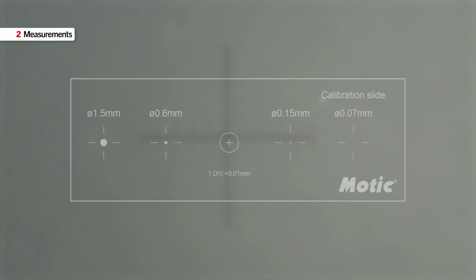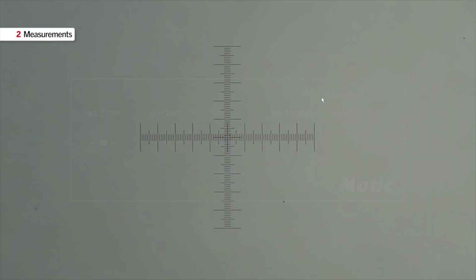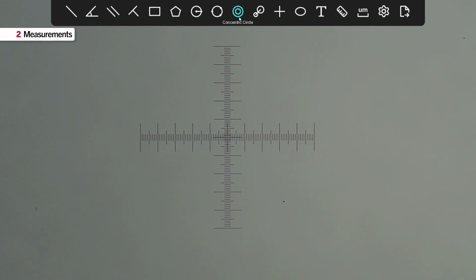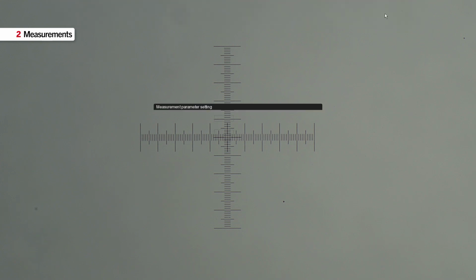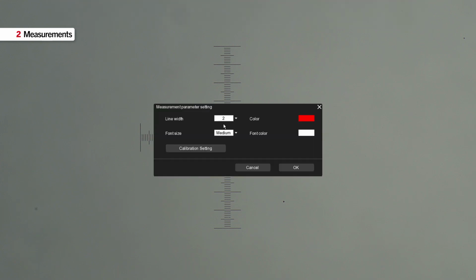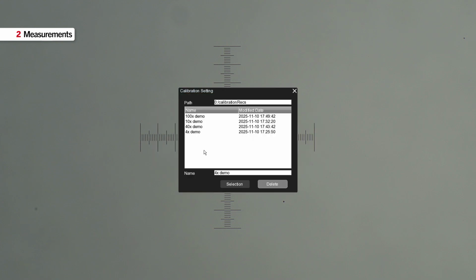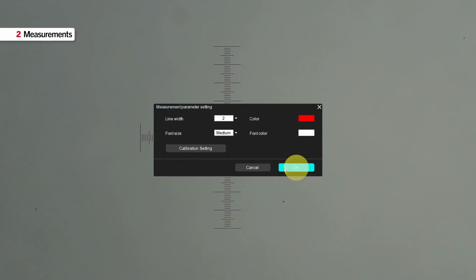To demonstrate this, we'll continue using the same micrometer cross from the calibration slide that comes with the camera. Go to the measurement toolbar at the top and click on Settings. Here, you can adjust visual preferences like line width, font size, and colors. Click the Calibration Setting button. From the list, choose the calibration associated with the objective in use, in our case, 4x demo. Then click Selection and Confirm with OK.